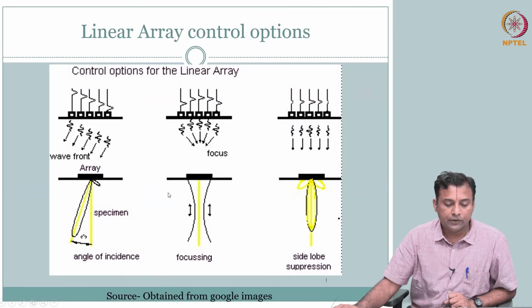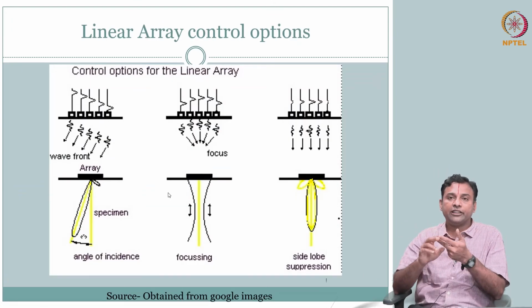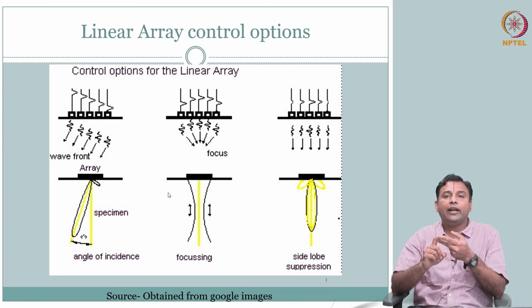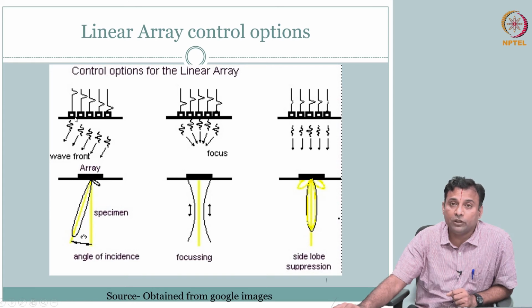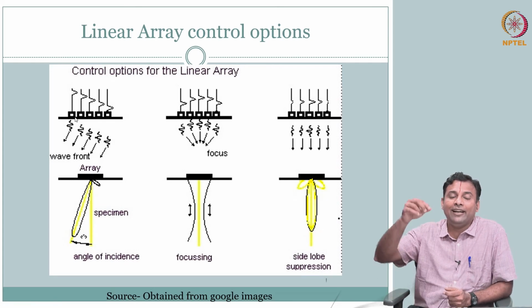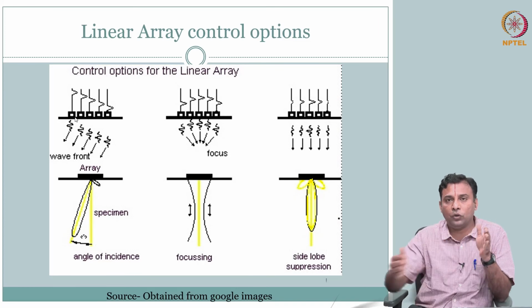Okay. So, why are we able to do this? So, different functionalities, why are we able to do this? The reason is here. Essentially what happens is, it becomes complex because now instead of having only one lead, we had a transducer, we had one wire coming out. So, you supply an electrical voltage, an electrical pulse, it will vibrate, sound goes out.